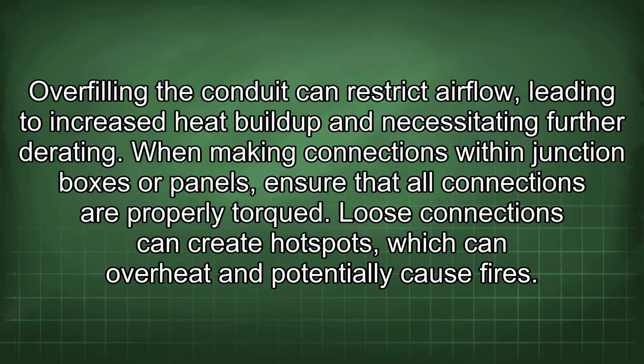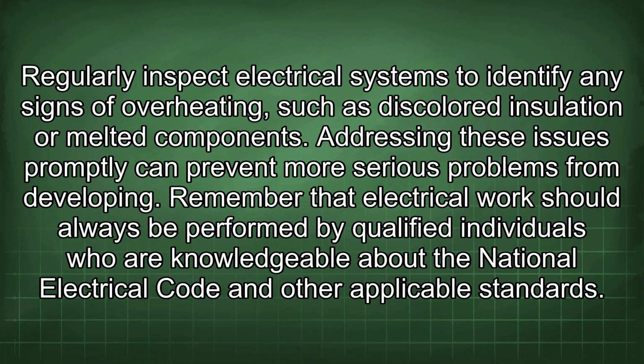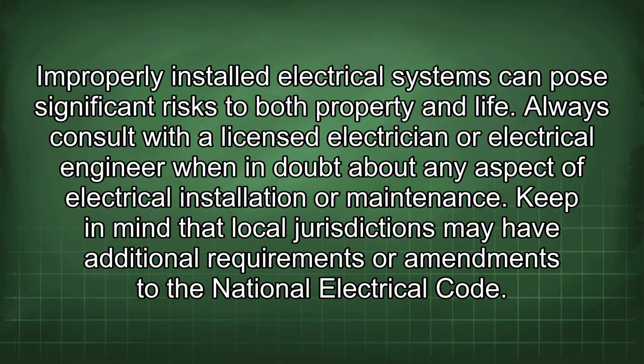When making connections within junction boxes or panels, ensure that all connections are properly torqued. Loose connections can create hot spots, which can overheat and potentially cause fires. Regularly inspect electrical systems to identify any signs of overheating, such as discolored insulation or melted components. Addressing these issues promptly can prevent more serious problems from developing. Remember that electrical work should always be performed by qualified individuals who are knowledgeable about the National Electrical Code and other applicable standards. Improperly installed electrical systems can pose significant risks to both property and life.